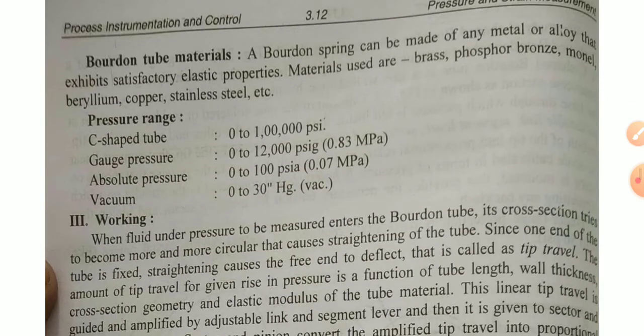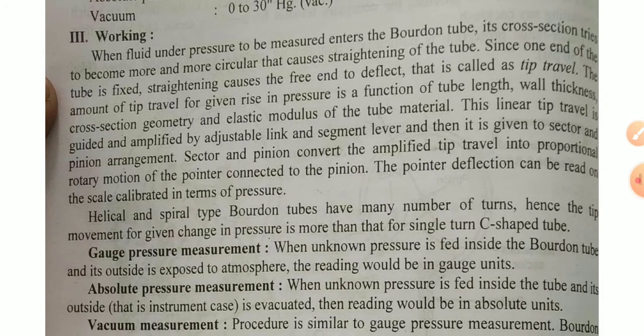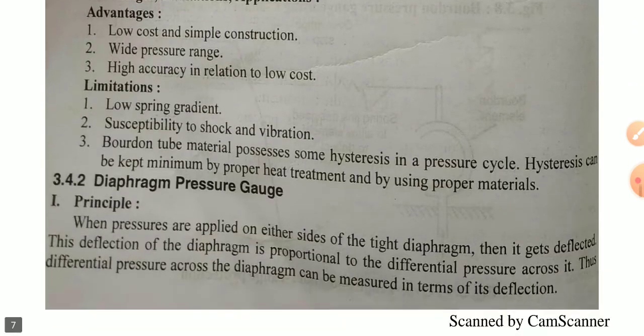All the discussion part. For the Bourdon tube material, a Bourdon spring can be made of any metal or alloy that exhibits satisfactory elastic properties. Materials used are brass, phosphor bronze, Monel, beryllium copper, stainless steel, etc. Some ranges are given, and the working part, advantages and disadvantages.